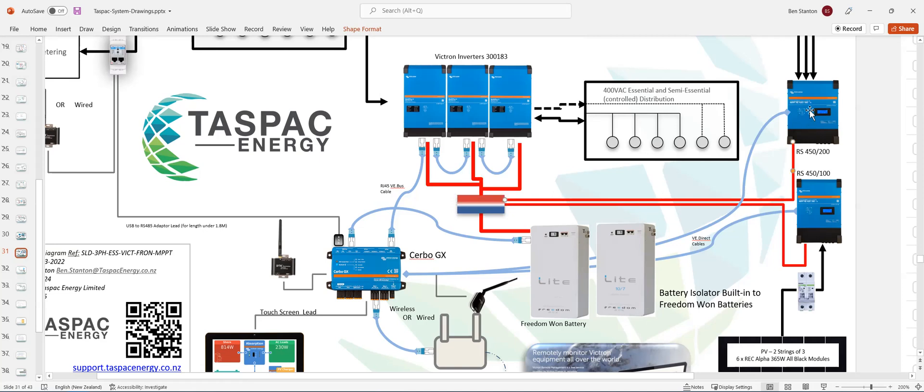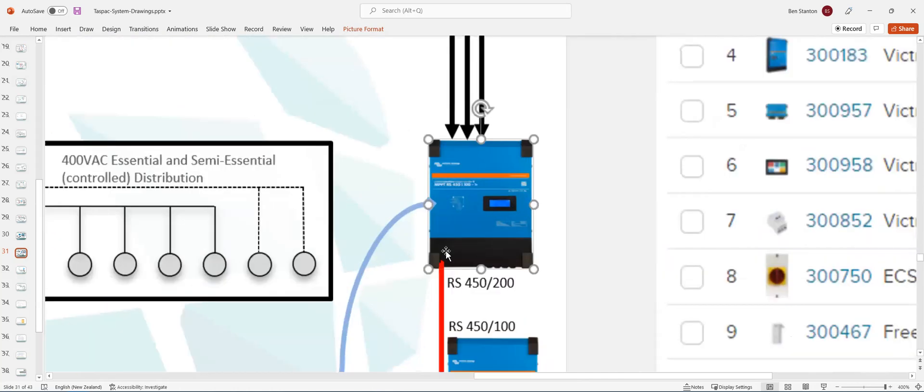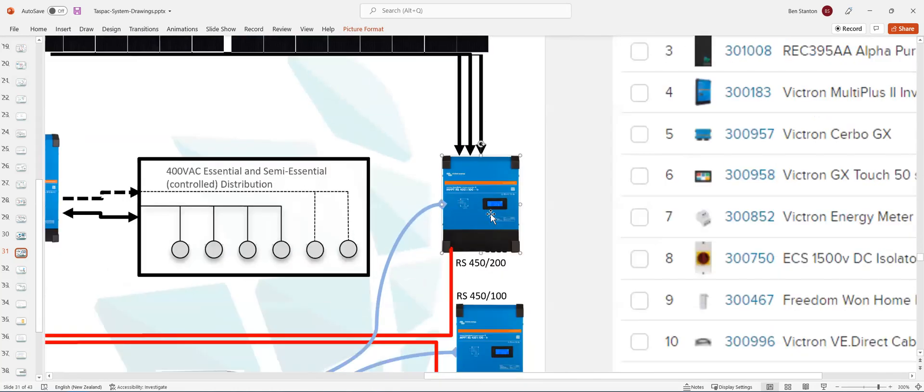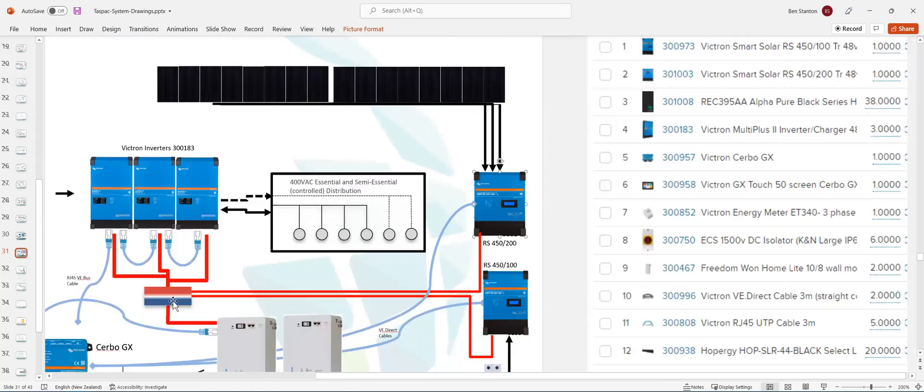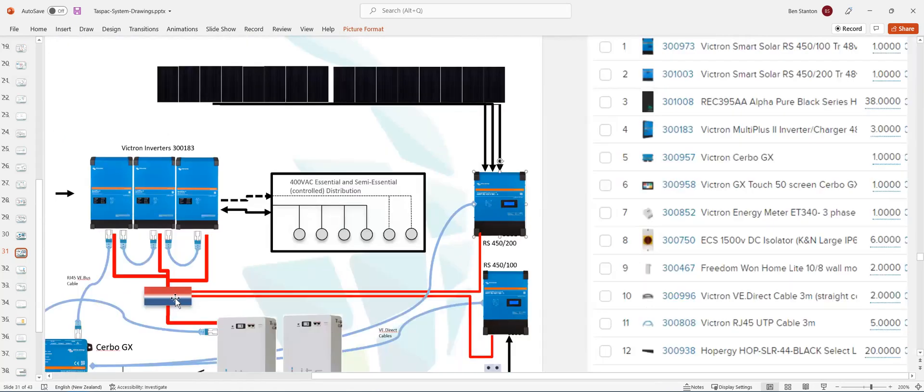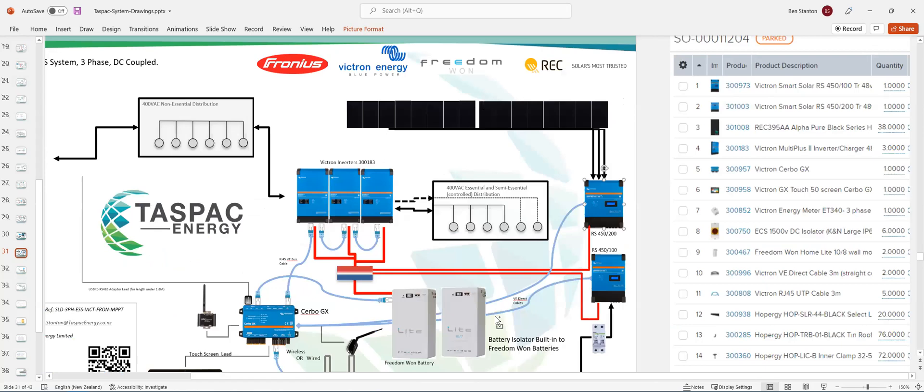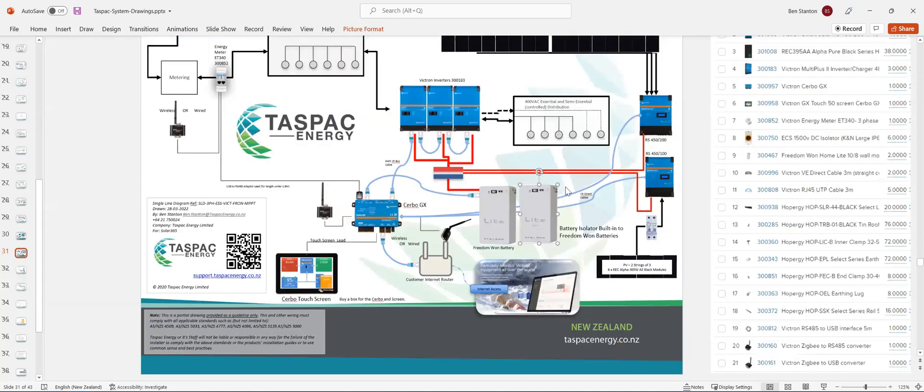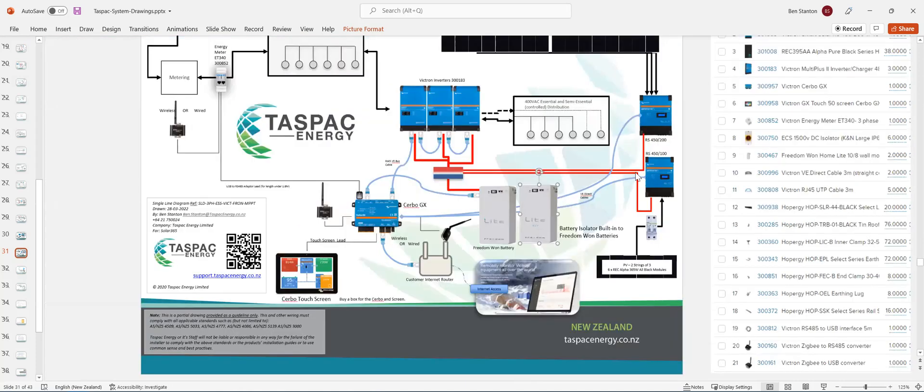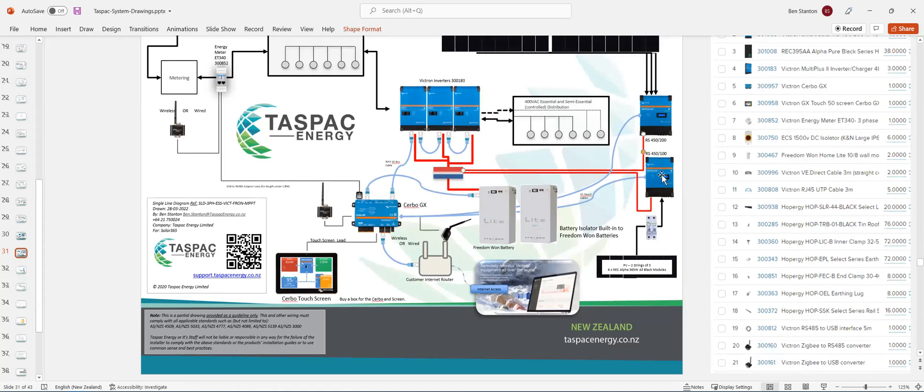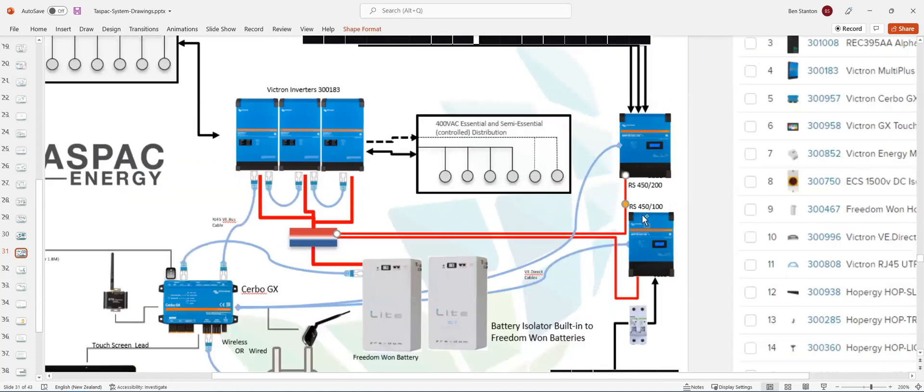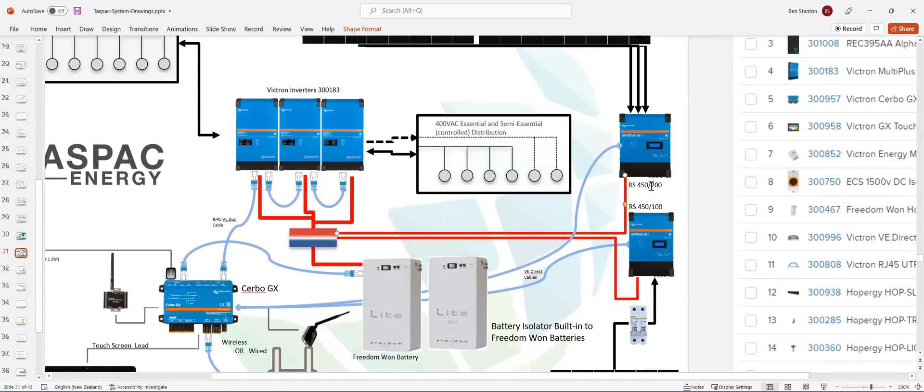Now, positive and negative are also going to come from your charge controllers. So these are the charge controllers. They're going to be connected to the bus bar with positive and negative cables. It doesn't matter about the length of the cables, so long as you don't get too much voltage drop. But it really doesn't matter about the length because the batteries are controlling the voltage. And you just need to make sure that the rating of the circuit breaker on the battery is less than what the cable can handle.